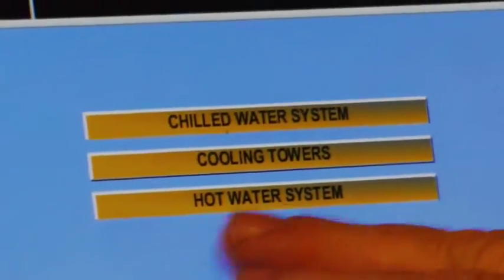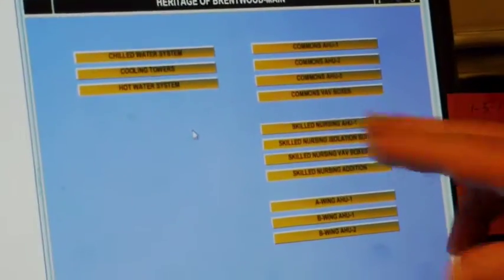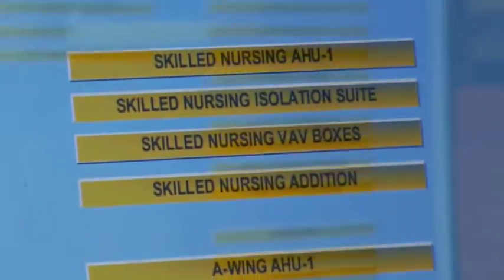This is what they call the Medisys system. This Medisys system controls almost every facet of the heating and cooling system in the community. For example, I have several options on here. I can monitor the chilled water system, I can monitor the cooling towers, I can monitor the hot water system. I have air handlers that are 3 main air handlers to the commons area, which is the clubhouse, dining room, and so forth like that. And then I have control of those VAV boxes there. We have the nursing center, and then A and B wing. So this system controls all the heating and air, chilled water system.